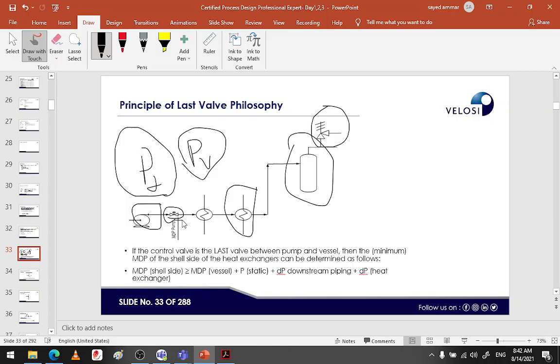As an owner, you simply will ask for a valve here and another valve here for maintenance purposes if you want to clean this heat exchanger, right? Correct. Yes. And during the HAZOP you will simply say that one of your operators closes a valve by mistake. That will lead to redesigning all this according to the shut-off pressure of the pump. You got it? Yes. Correct. It is like a game by the end of the day. The EPC contractor doesn't want to pay a lot of money for valves, and the owner wants a lot of valves.